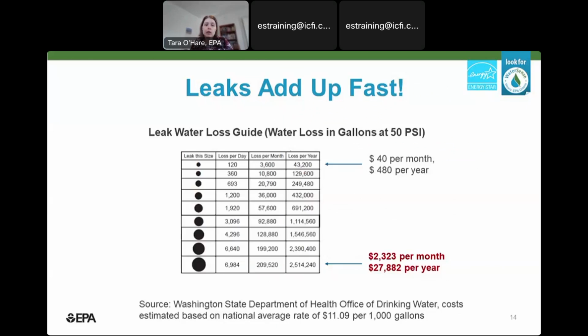So I wanted to give you a little bit of an impression of what the magnitude is that I'm talking about. So we put together this chart. Actually, Washington State put together this chart. And this is really just to show you, at a certain size hole in a pipe, what that actually equals in water savings if you fix it. So you can see it starts kind of small, but it still adds up to about $500 per year in water use. And then as you get to a larger hole in the pipe, it's quite a bit more, almost $30,000 per year. And so it's really something significant to pay attention to.